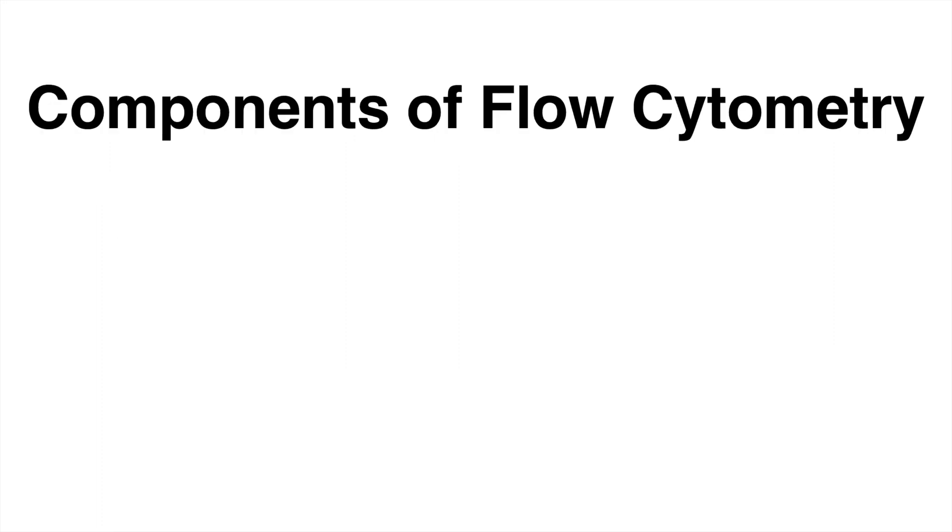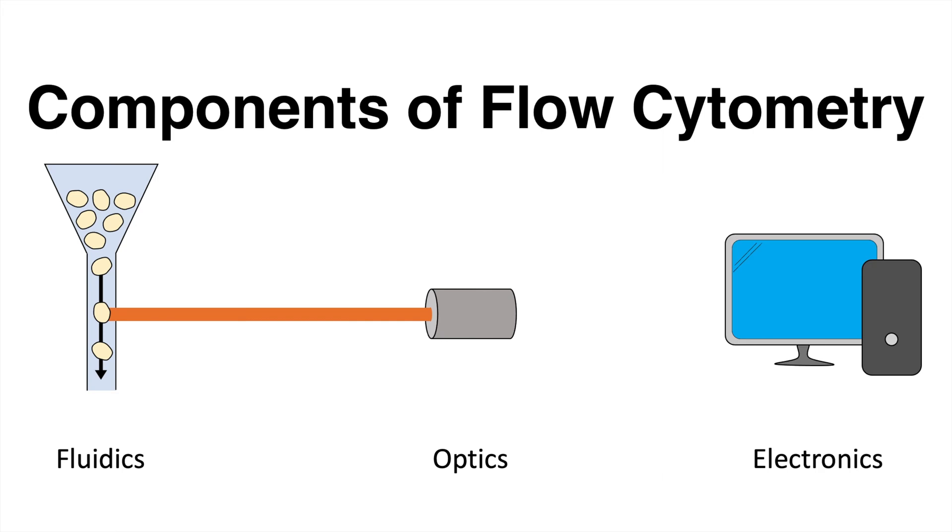It is based on three systems. The fluidic system enables cells of a suspension to be squeezed through a fluidic stream one by one. The optic system involves lasers and detectors, and electronics translate signals into a dataset.